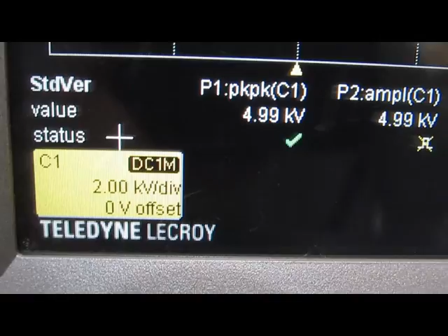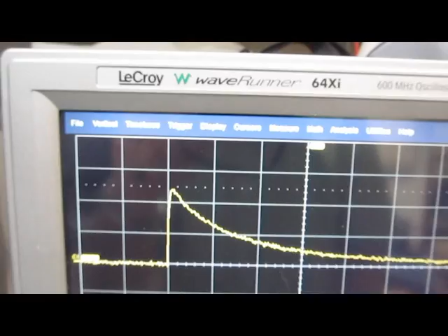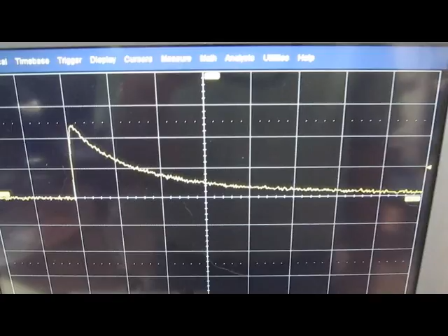So looking at the LeCroy, you can see we're 5 microseconds per division, 2000 volts per division vertically, and basically 5 kilovolts. The last test was at 3.7 kilovolts, and we've jumped it all the way up to 5 kilovolts. I'm comfortable now that the meters that remain probably do pass their standard, so that pulse would be 6,000 volts. You can see here too, the decay is slightly shorter.